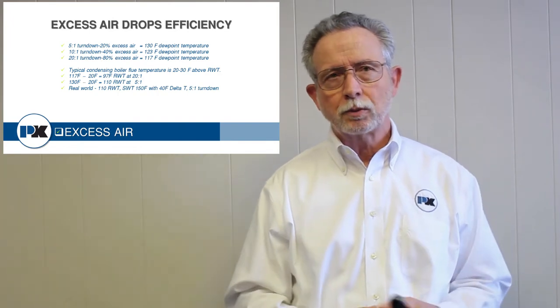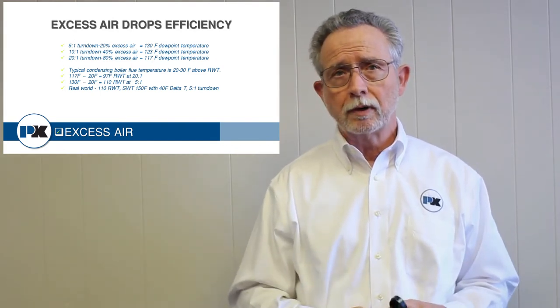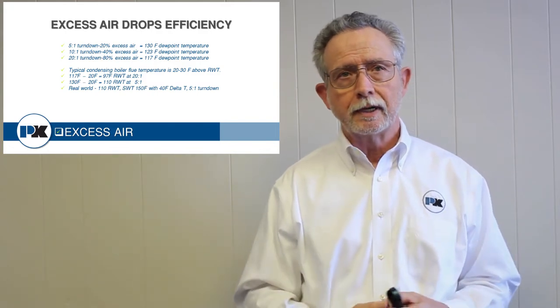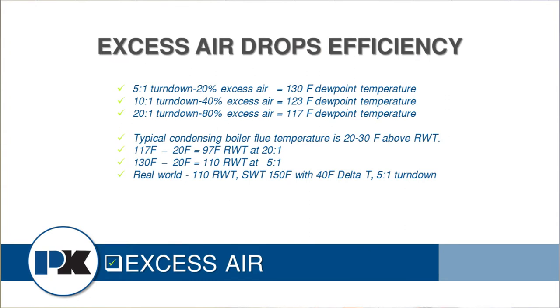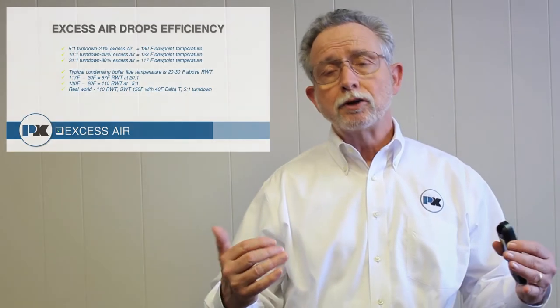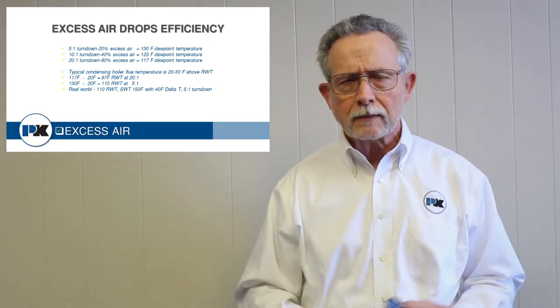On a five to one turndown we use approximately 20% excess air, which gives us the highest dew point possible — around 130 to 135 degrees depending on relative humidity. At ten to one turndown you're adding about 40% excess air, which drops the dew point to around 123 degrees. At twenty to one turndown you need 80% excess air and the dew point drops further to about 117 degrees.